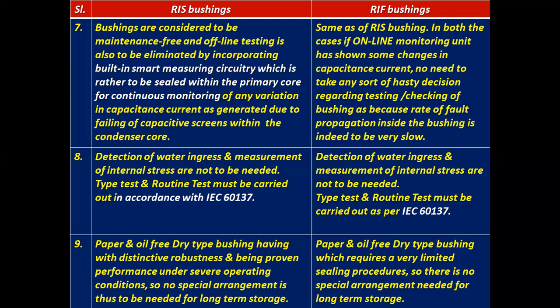The same as for RIS bushing, in both cases, if the online monitoring unit shows some changes in capacitance current, there is no need to take any hasty decision regarding testing or checking of bushings, because the rate of fault propagation inside the bushing is very slow.